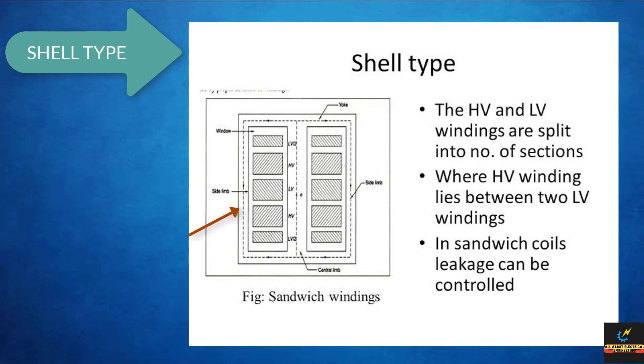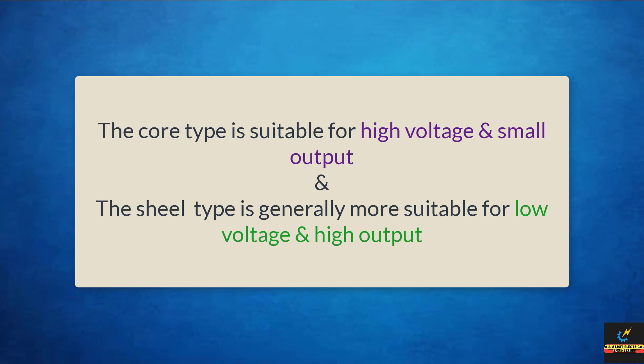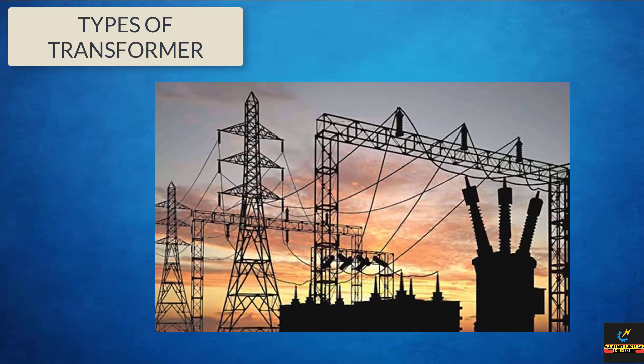The other two limbs are acting simply as a low reluctance flux path. Now, the choice of type of core, whether core or shell type, will not generally affect the efficiency of the transformer. The core type is generally more suitable for high voltage and small output, while the shell type is generally more suitable for low voltage and high output.